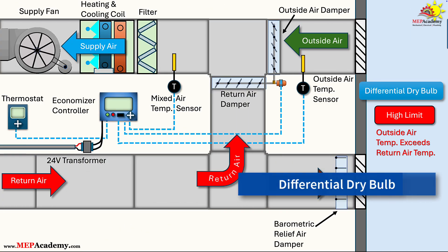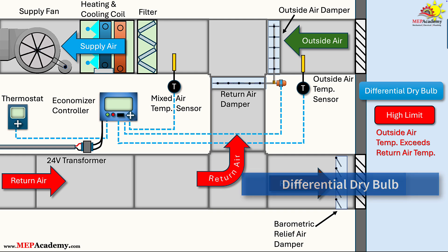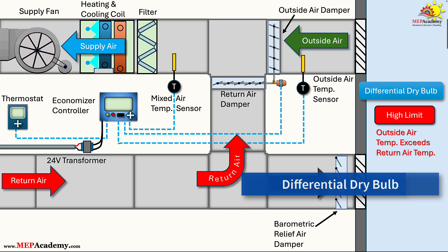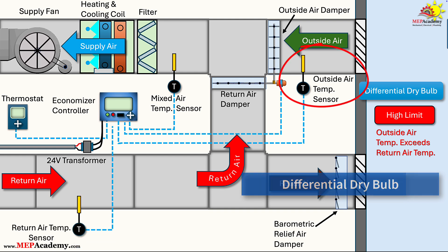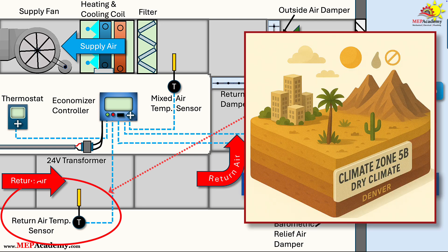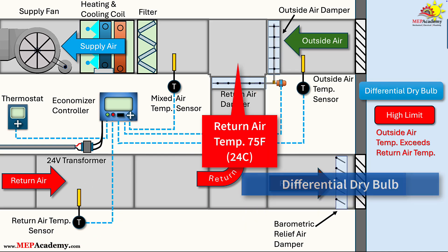Differential Dry Bulb Strategy. The differential dry bulb strategy improves upon the fixed approach by comparing the outdoor air dry bulb temperature to the return air temperature from the building. The economizer disables only when the outdoor air is warmer than the return air, allowing for more dynamic operation based on actual indoor conditions. This requires two temperature sensors – one for outdoor air and one for return air. For example, in a data center in a dry climate like Zone 5B, such as Denver, the return air might be at 75°F due to internal heat loads.